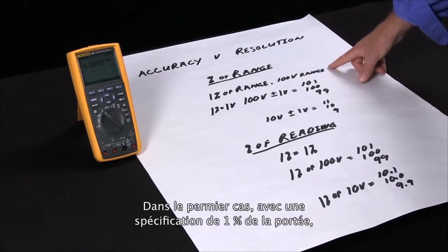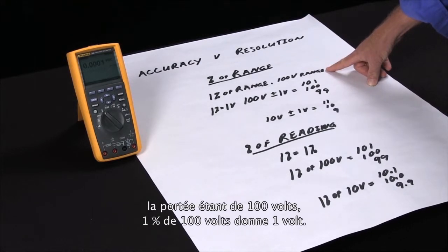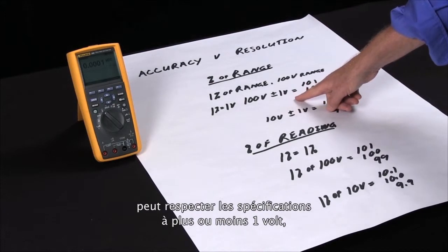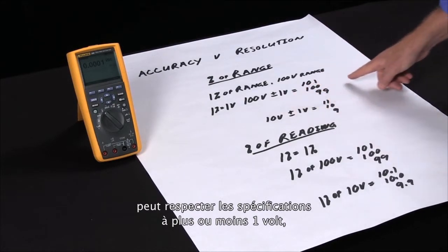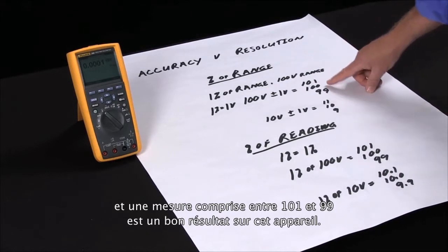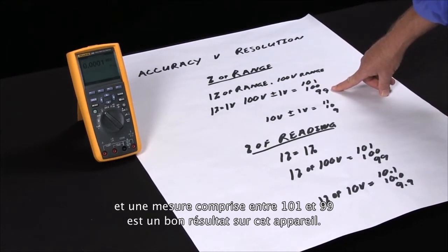For percent of range, if we have a one percent specification of range and we're on a hundred volt range, one percent of a hundred volts is one volt. So that means with a reading of a hundred volts that can be within specification at plus or minus one volt. So a reading between a hundred and one and ninety-nine is actually a good reading on this meter.